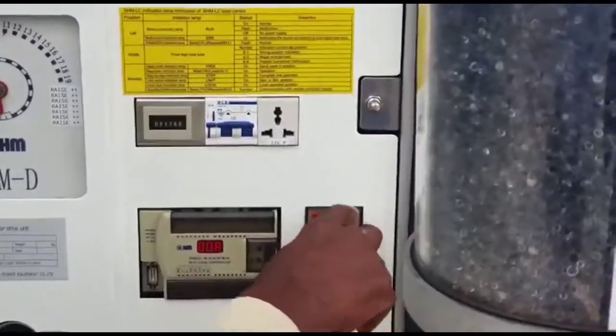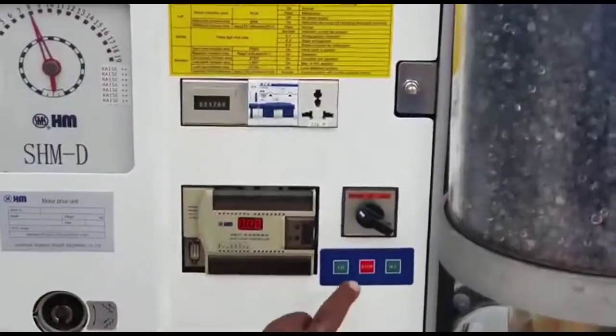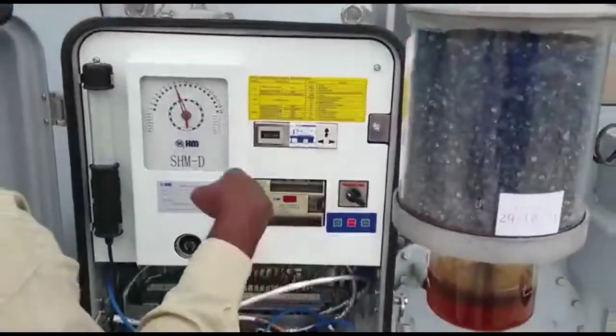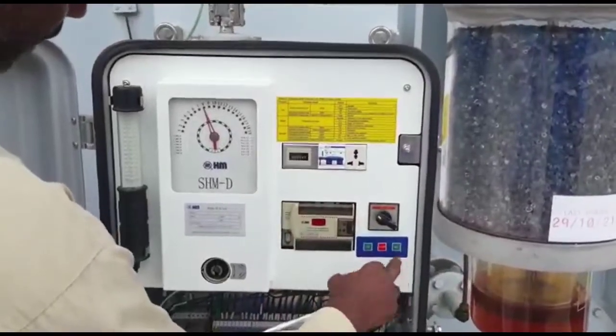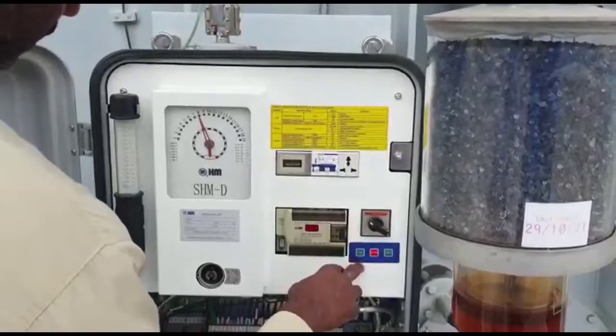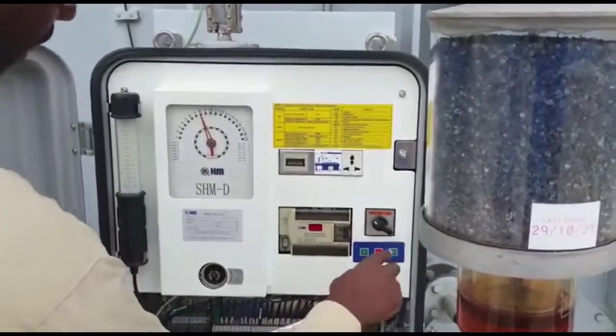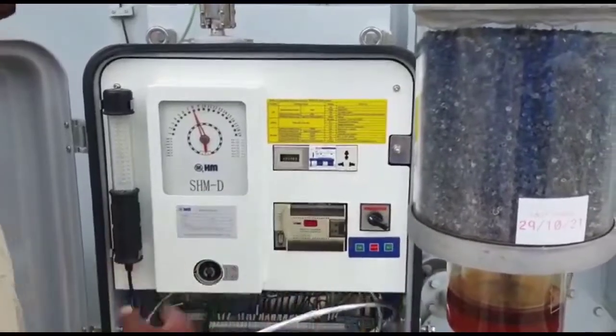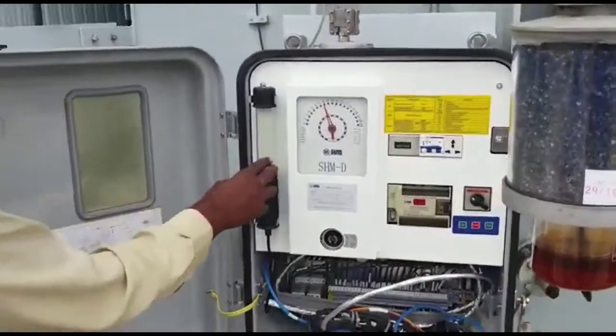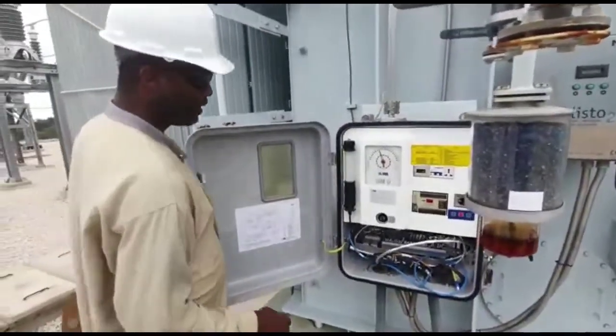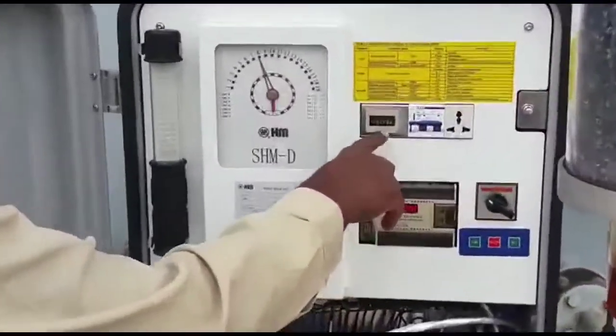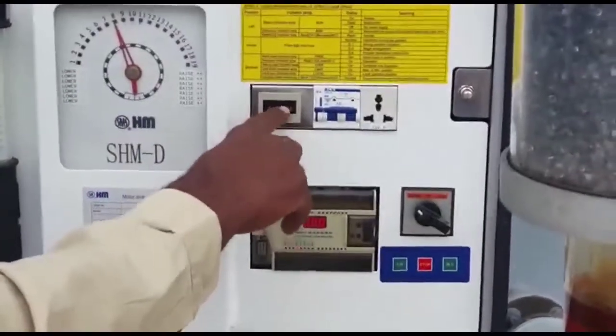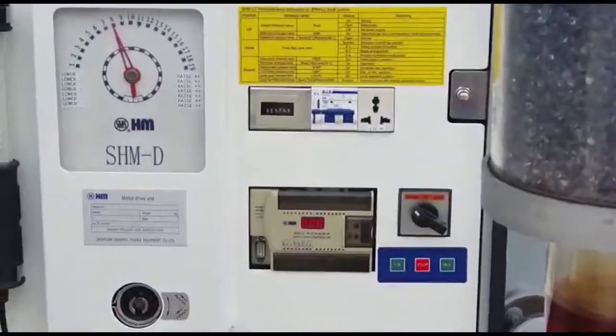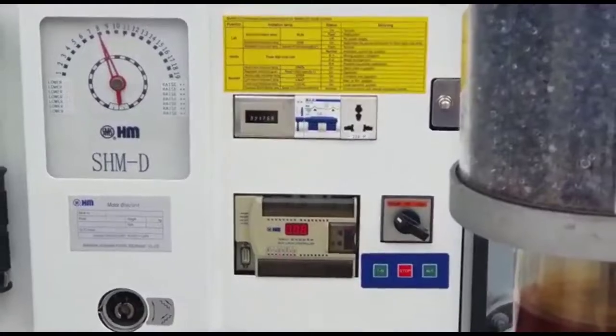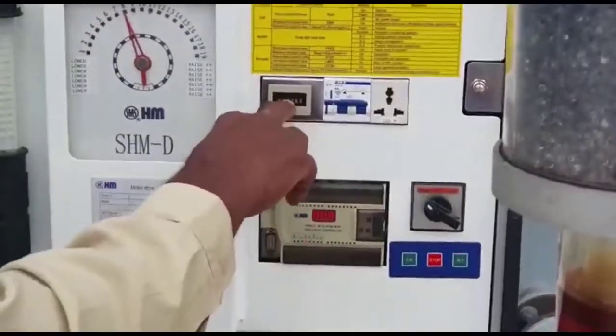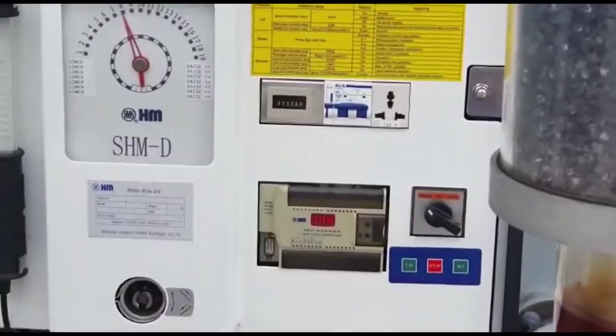When it's in local, you physically stand here and press the plus sign if you want it to go up. You press the minus sign if you want it to go down. So N minus 1, or the plus sign underneath, will go up, and N plus 1, or the minus underneath, will go down. You have a light here that you can use if it's night. You also have the tap settings display here. We have the tap counter here, which tells you the total amount of tap operations this transformer has had over its lifetime. So this tells you the number of times this tap has changed since this transformer has been here.